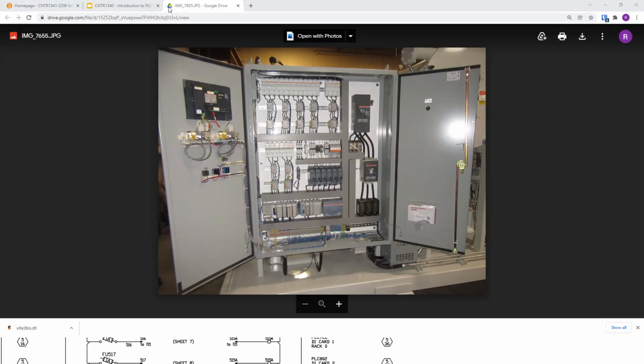Essentially, this whole system is for oil processing. So you've got your main breaker. The top is all heaters, so those are all fuses for heaters. I think they're 60 amp fuse holders, so we probably have 50 amp fuses in there. The reason there is a contactor above and below is because the customer wanted a redundant contactor for safety reasons. I think this one might have been processing kerosene, so they wanted a little more safety with that.